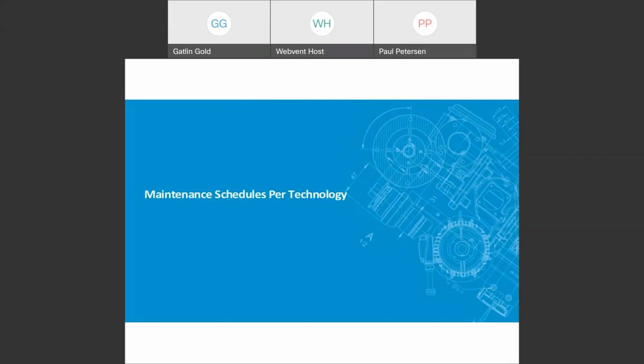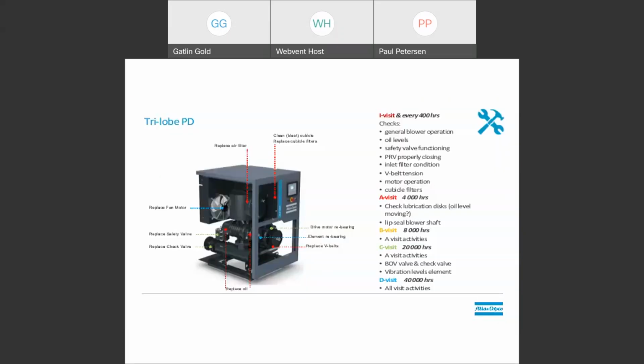So regarding maintenance, we're going to go through a few of the maintenance activities for the most common types of blowers, like Paul had discussed in our summary in the beginning. And just to keep things simple, I'm typically going to refer to 1 year of 24/7 operation as about 8,000 hours. So when I say annually or biannually, we're looking at generally 8,000 hours and 4,000 hours, respectively.